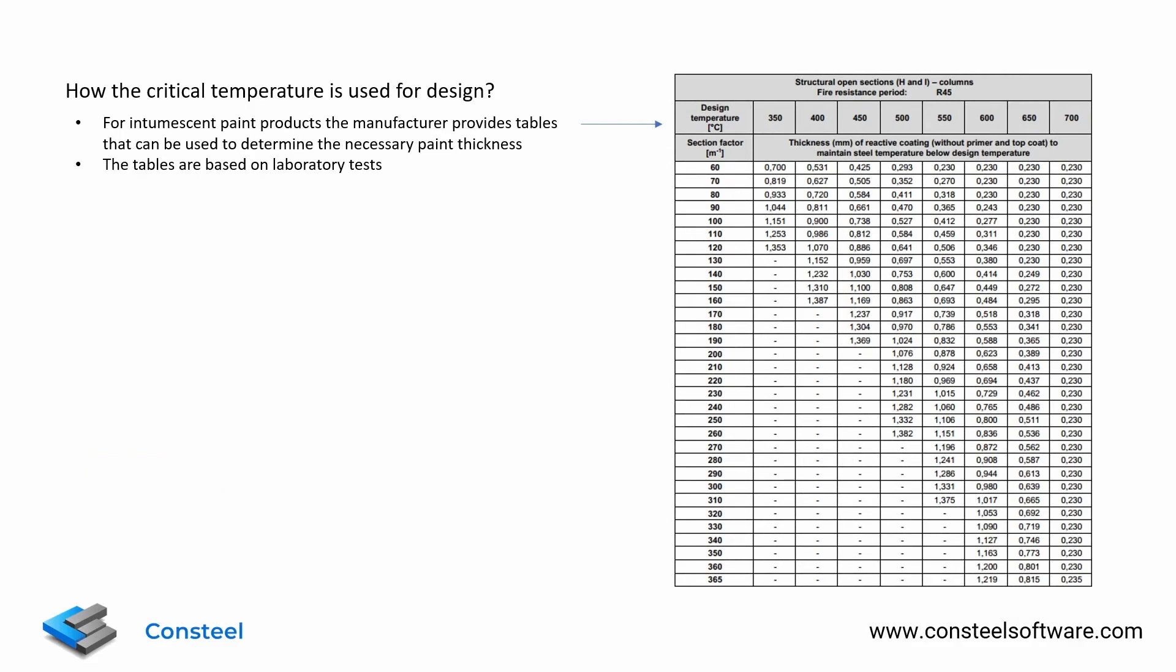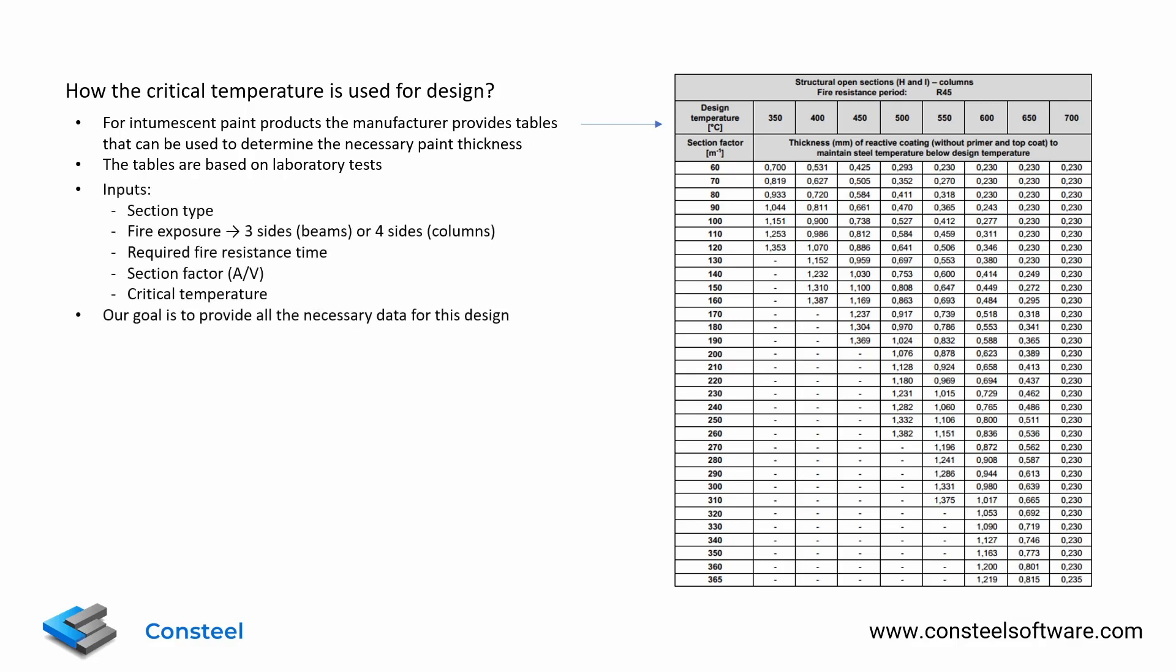In case of intumescent paints, laboratory tests are carried out to determine the necessary paint thickness for a range of possible cross-section types and critical temperatures. The results of these tests are compiled into tables that the manufacturer provides for their specific paint product.